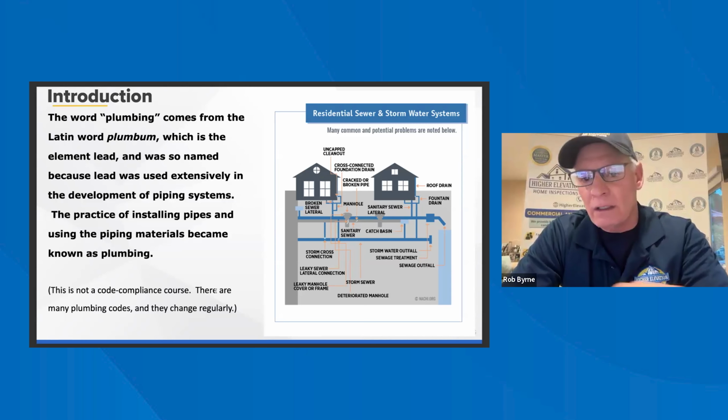Water consumption, again, these are just what you would get at a shower head, a sink, a urinal. Not that you need to know it, but it's information. Federal law mandates that sink faucets have a maximum flow of 2.2 at 60 PSI. If not, it's not going to function properly. You're going to write it up anyway. You're not going to figure out the gallons per minute or anything like that, but you'll see restricted flows at the shower head, the sink, the toilets. You would definitely comment on that.